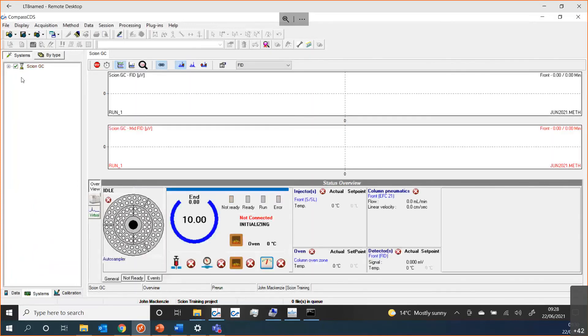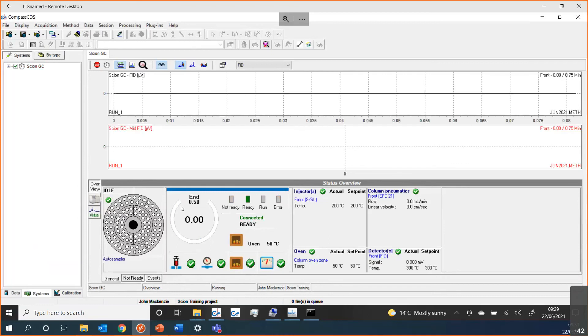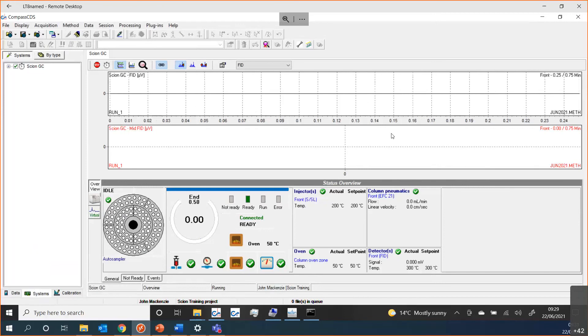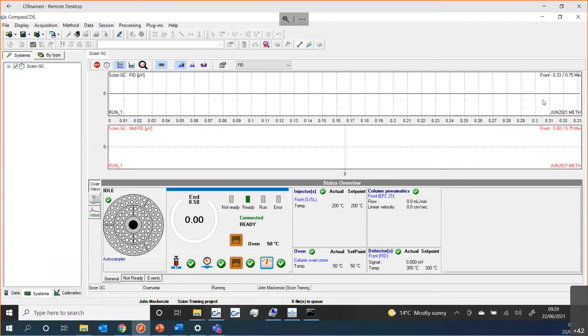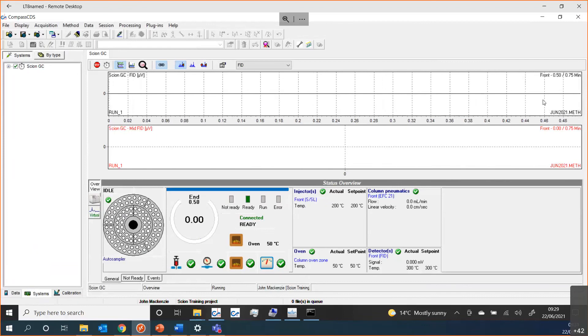Let's go look and see what we get for our analysis. While our analysis is running, we can actually see what's going on, what it's doing. It says it's in pre-run. It says my GC is ready. It's waiting for the injection and it's now going to running. Hopefully we will get some data collected here. Yes, there we are. My B channel is not doing anything. There's something definitely a bit strange going on here. We should see some peaks. We should have seen some peaks by now. This is what happens when you fly without a safety net. Sometimes things don't quite work out the way that you anticipate.